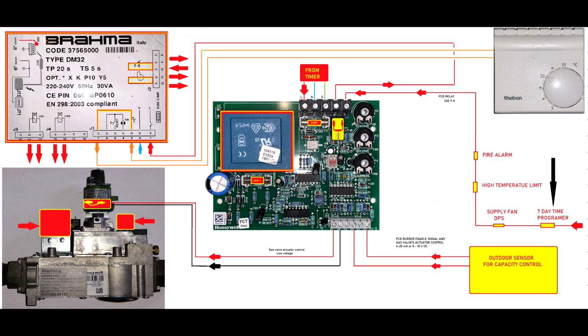So this is all good. You have a timer, and because you like safety, you will not only provide the signal to that relay on the printed circuit board, actually you will provide power to the circuit board. So when the timer finishes its duty, it will cut the power to this printed circuit board. This way it's much safer. If you have any leak or let-by of electricity, you won't have any problem.